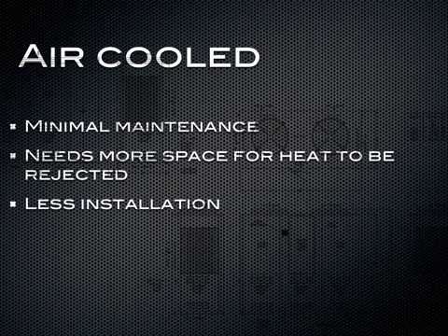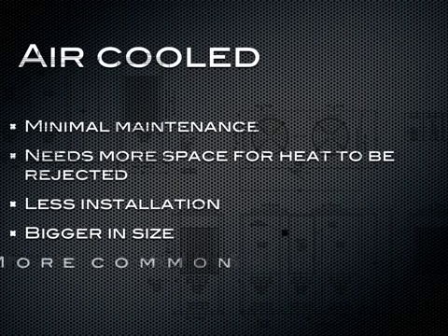There is less installation in an air-cooled chiller because they stand alone. They don't need a cooling tower or building water like a water-cooled chiller does. They are bigger in size compared to a water-cooled chiller because those condensers and fans are much larger than the condensers on a water-cooled chiller. They are more common because they do stand alone.